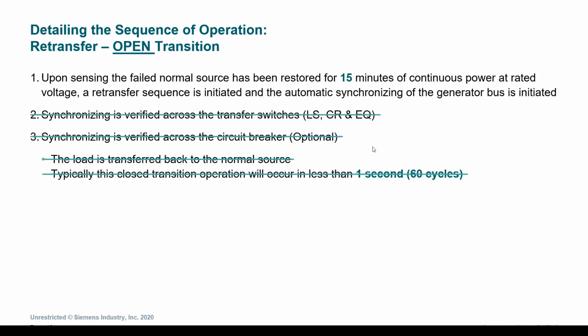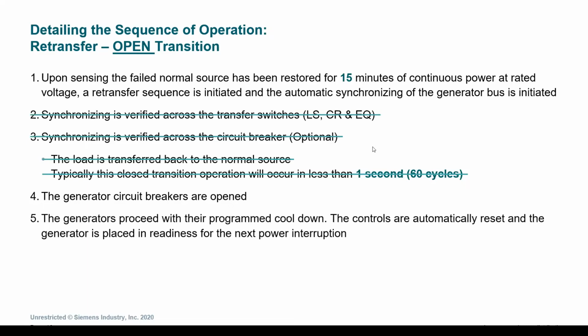There is no synchronizing across any of the transfer switches or any of the circuit breakers. All of the transfer switches go from emergency to normal source, and that interruption occurs. From here, the generator circuit breakers are opened, and again, the generators, similar to before, proceed into their program cooldown and are automatically reset and placed in readiness for the next power interruption. And again, at this time, the system is returned to its normal operation.